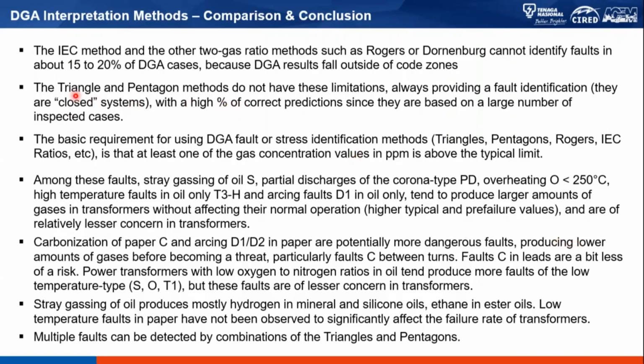that is very different from the triangle and pentagon method developed by Professor Duval, whereby it has no such limitation. Whatever you are calculating, it will define the fault for you. It will never give you something that is unidentified. It will always give you a result on the type of fault that is occurring inside the transformer. Whether or not it's accurate is something else, but it will give you an answer.